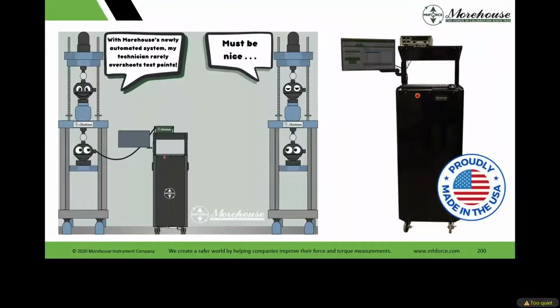Look, the automated UCM controls the force much better than technicians. Your R&Rs become better, your repeatability becomes better. The technician sets the load cell up in the machine, and the machine just runs. They go rotate it if they're doing E74, do whatever else, set up or warm up another thing, and run data. What's happening in our industry is that technicians are hard to find.